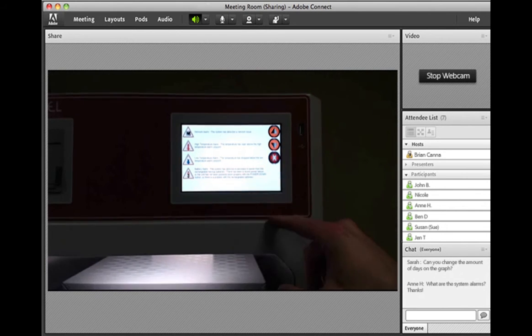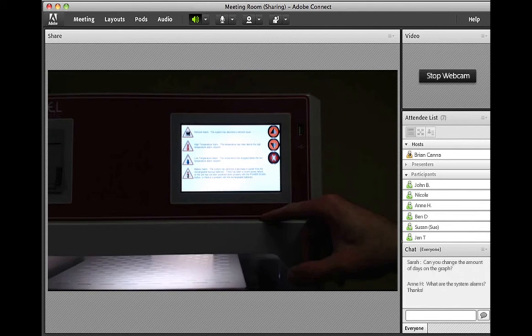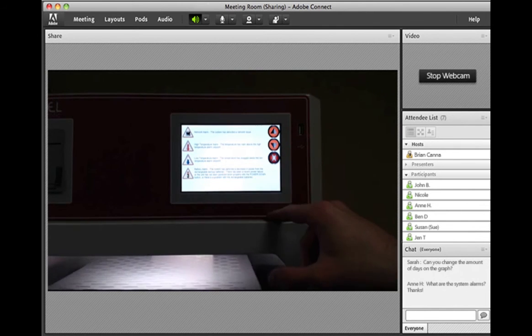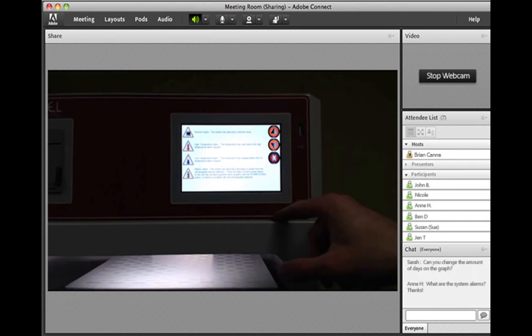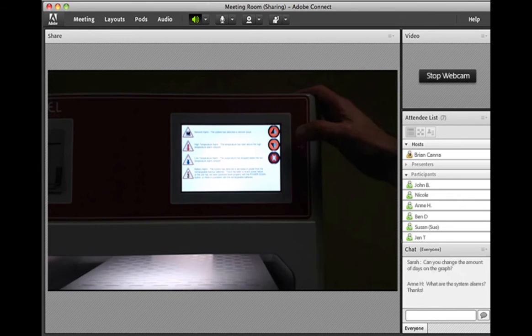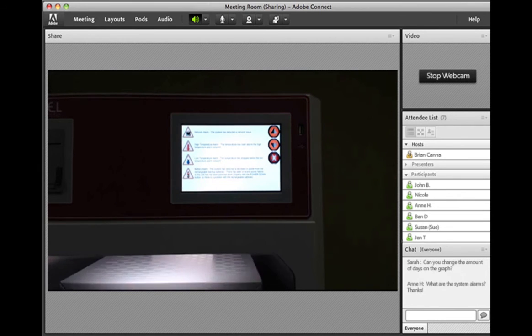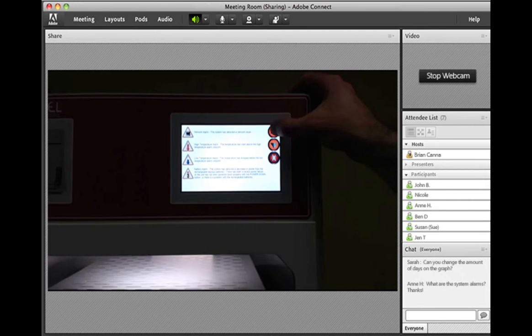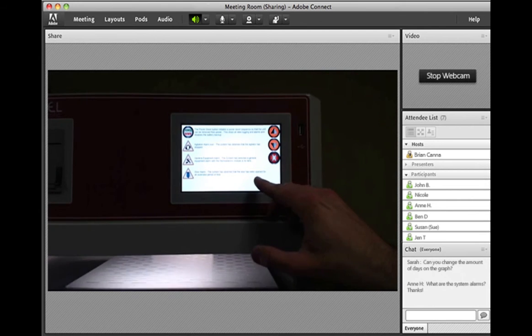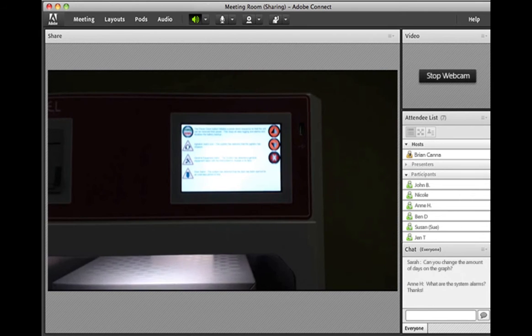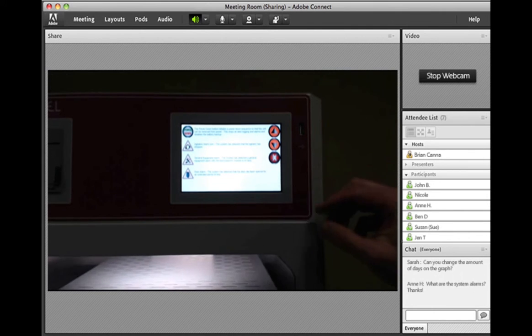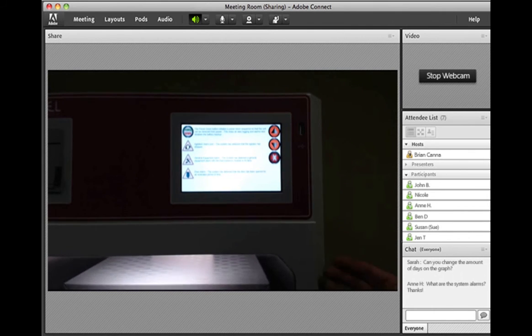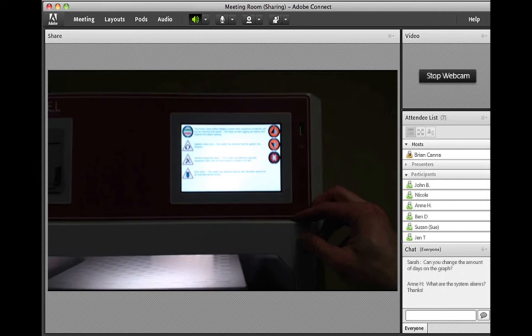So this is our low temperature alarm. If you go below that 20.5 degrees C, you will get that low temperature alarm. Our high temperature alarm, if you go above 23.5 degrees C. You have your network alarm. So if you do have this hooked into a system and it detects an issue with that connection, you will get an alarm with that. You have your door alarm. So if you open the door and you leave it open for an extended period of time, I believe it's 2 minutes, you will get a warning because the inventory could heat up or cool down and not be maintained at the proper temperature.